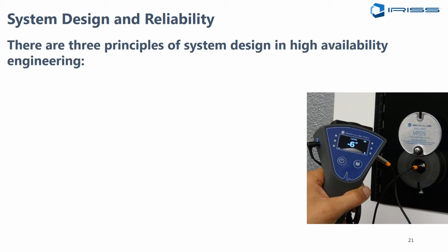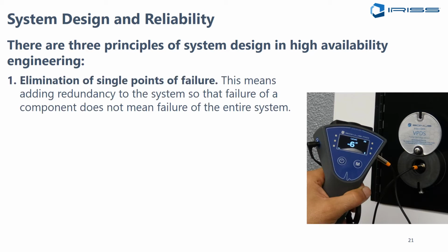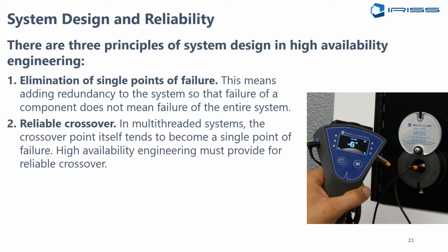Now, primarily there are three principles in system design for high availability engineering. Number one is we try to eliminate single points of failure, providing redundancy to systems, so failures of components don't mean complete or entire system failure. Secondly, we need reliable crossover points. Unfortunately, sometimes a crossover point tends to become a single point of failure, so high availability engineering provides reliable crossover.